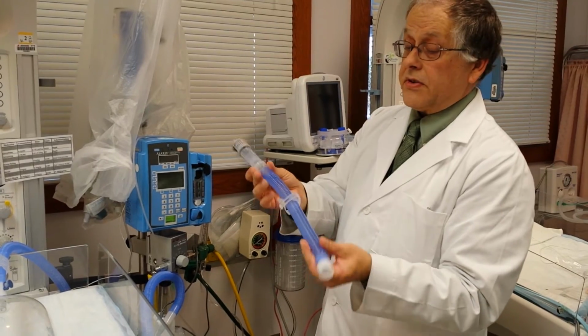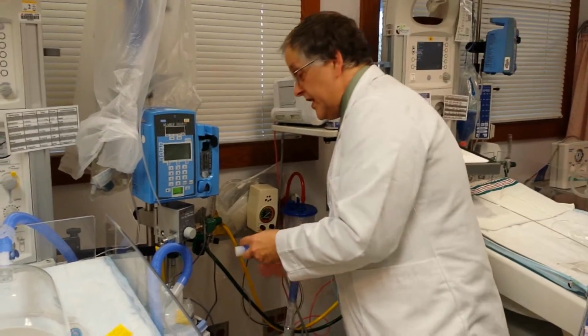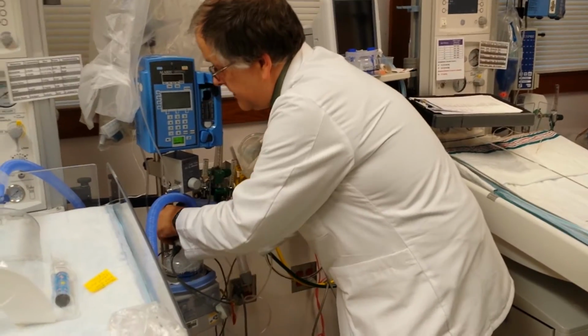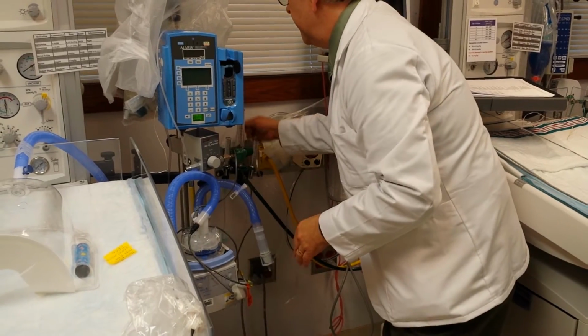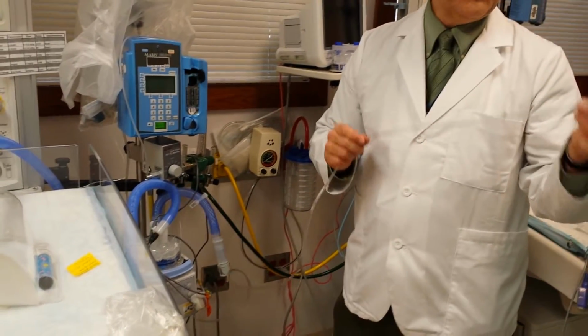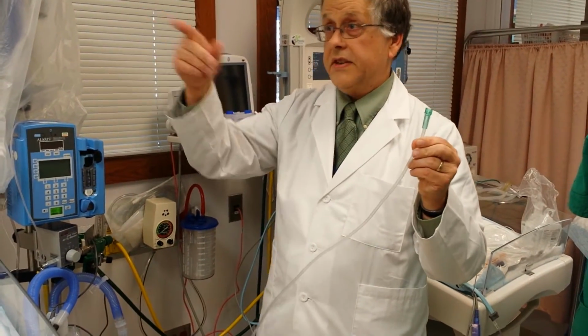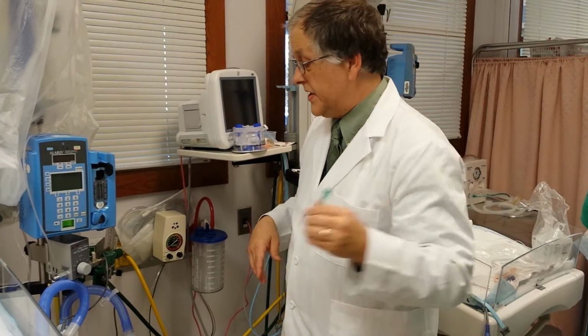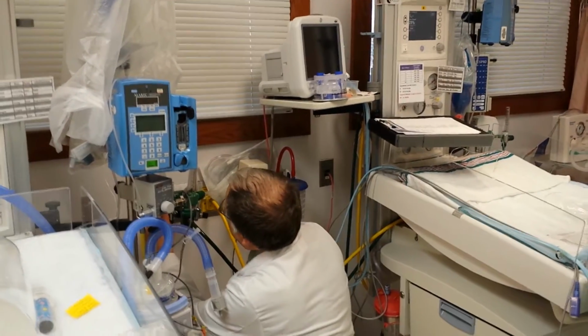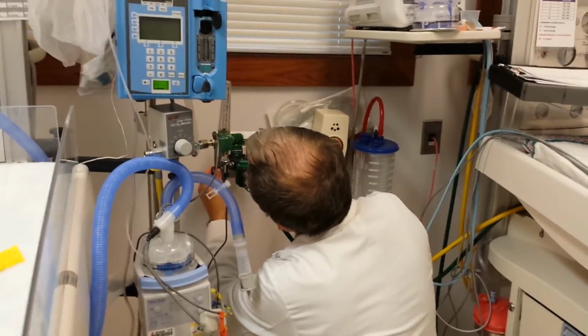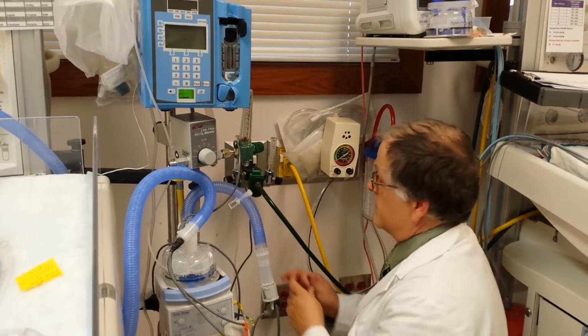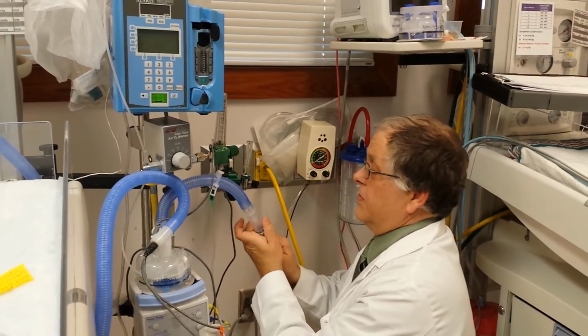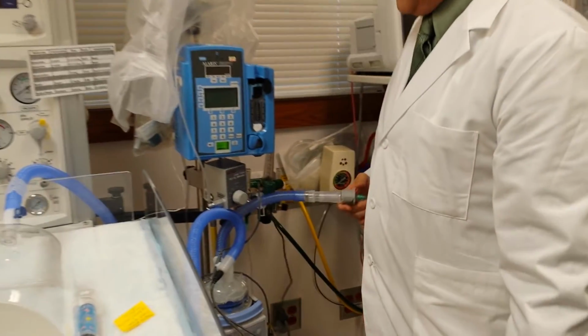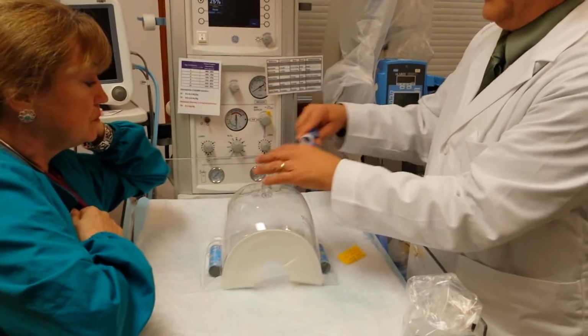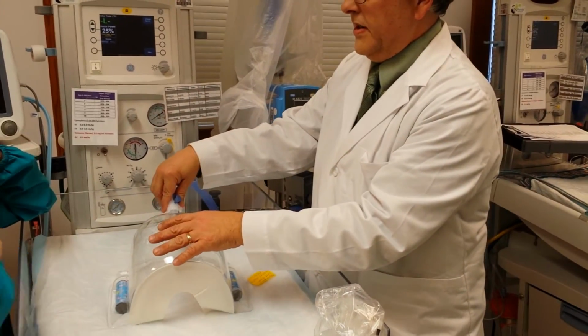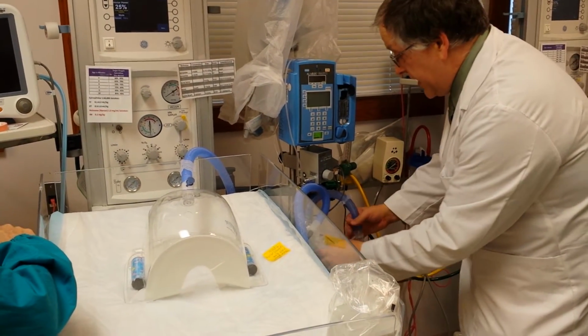So this attaches there. This is a little extension tube. It'll fit in there, but I like to use this. And then you put this here. Now, one thing that's not in your package, you need green oxygen connecting tubing. Okay, don't use that, the green pliable stuff. Green oxygen connecting tubing. You set your flow at the prescribed flow rate. Now it's 4, and that's the center of the ball right on the 4. Okay, and you put that to the Venturi nipple right there, and right away you start to hear a flow. Okay. And just to verify it, you'll feel a flow coming out there. Hook that up.